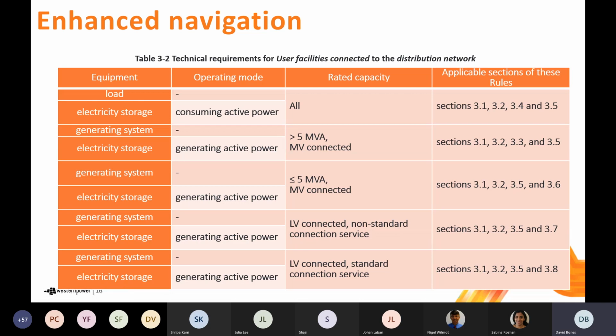And that's simply because there's a few more variations that needed to be considered when you're talking distribution connected facilities. So you've got the consideration both of the size of the generating system and on the voltage and the connection arrangements that apply. So whether you're connecting to the LV via a non-standard connection service or a standard connection service, and if you're connecting to the high voltage, then differentiated by the size of the connection. So we've separated out each of these. We believe that across these tables, then a user would be able to say, well, what facility am I looking to connect and which requirements need to apply?